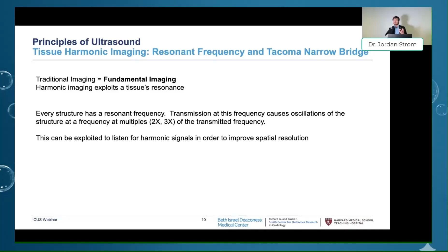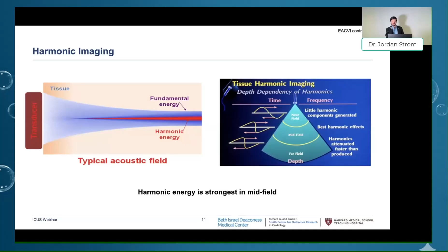So harmonic imaging is really greatest at the depth of where we use it for echocardiography, with about 10 to 20 centimeters from the transducer surface. So this is really helpful to not only improve our imaging of bubbles, but it's also helpful to improve our imaging overall, which is why second harmonic imaging is our standard preset on most echocardiography machines. And in the near field, there's very little harmonics that are produced, and in the far field, the harmonics are attenuated faster than they're produced. So that middle is the sweet spot.